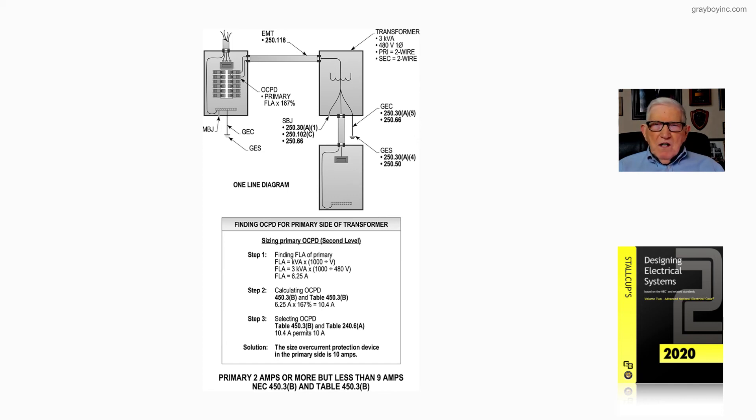Now, with this information given, as you see in the illustration, the overcurrent protection device in the primary side will be sized at 167% because the full load current of the transformer's primary side is less than 9 amps, but 2 amps or more. So next, we're going to perform the calculation.